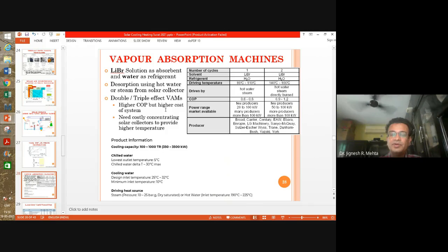So this is giving you the range of COPs. Let's say this is the single effect one, and this is the double effect. You can see for single effect you need a lower driving temperature, 80 to 100 degrees, 110 degrees, and for double effect you can see the number of cycles, that is effects or the stages. So here you need higher temperature water or steam, and you get a COP in the range of 0.6 to 0.8 for single effect. For double effect it can increase from 0.9 to 1.2.